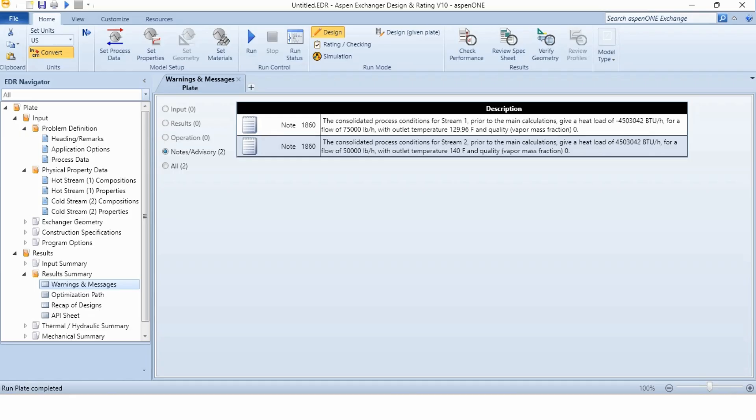For the cold stream, the second stream, the consolidated process conditions for stream 2 prior to the main calculations give a heat load of 4,503,042 BTU per hour. So the amount of heat transfer from the hot stream is equal to the amount of heat gained by the cold stream, for a flow rate of 50,000 pounds per hour with outlet temperature of 140 degree Fahrenheit. And again mass fraction, vapor fraction is 0 in the system.